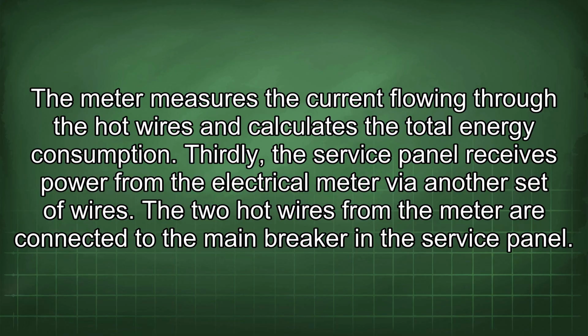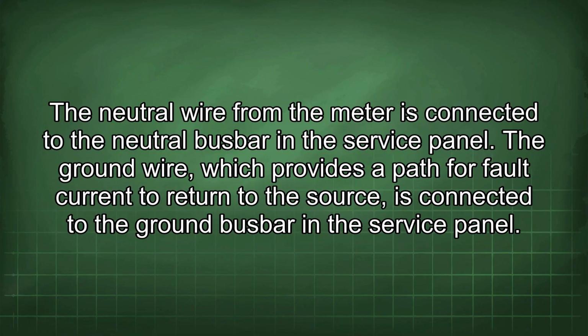Thirdly, the service panel receives power from the electrical meter via another set of wires. The 2 hot wires from the meter are connected to the main breaker in the service panel. The neutral wire from the meter is connected to the neutral busbar in the service panel. The ground wire, which provides a path for fault current to return to the source, is connected to the ground busbar in the service panel.